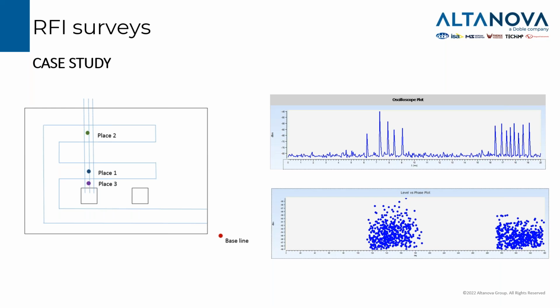One key point that can be interesting when speaking about surveys is that they can be easily included in the routine maintenance of a substation. So we will have the local personnel of the substation, who know more or less every detail of the substation, taking these readings, and just by a direct comparison between the past readings and the new readings they can highlight eventual problems occurring in the substation.